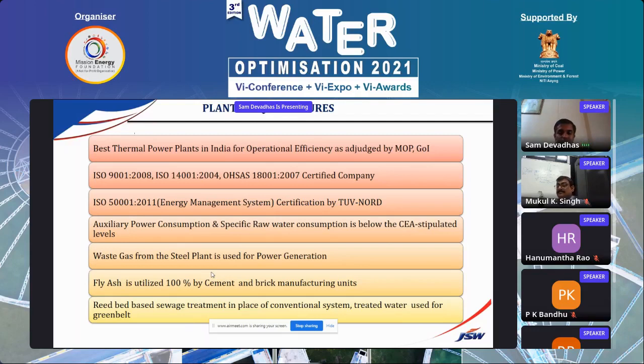Especially in our 130 megawatt plant, 100% gas as well as 100% coal can be used, but presently we use about 40% of generation through the byproduct gas. In the other 300 megawatt units, about 10% of power generation is done by waste gas. Fly ash is used 100% by the cement industries and local brick manufacturing units.